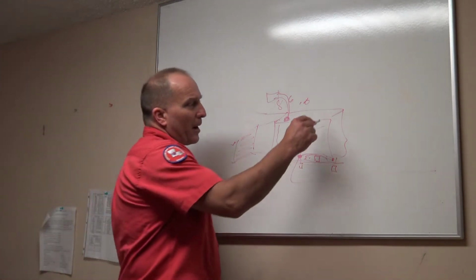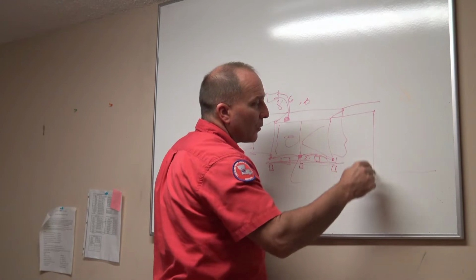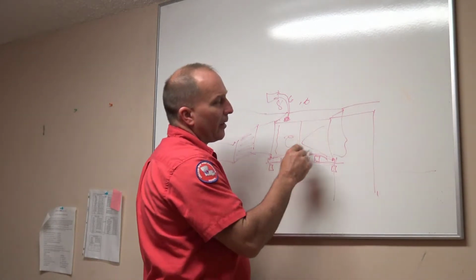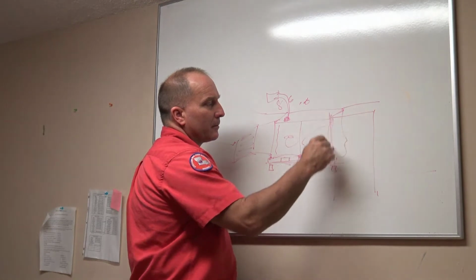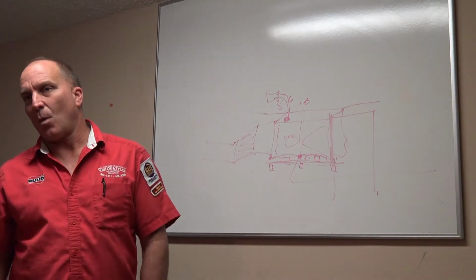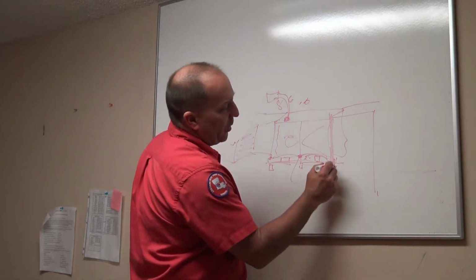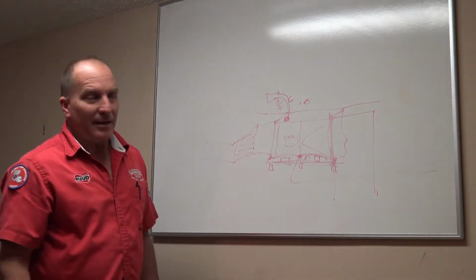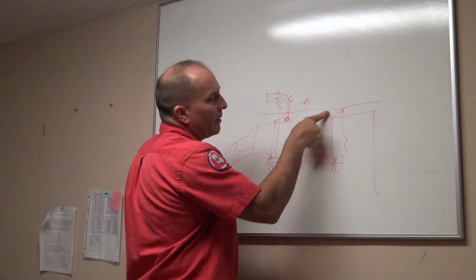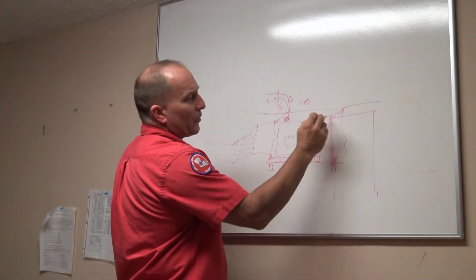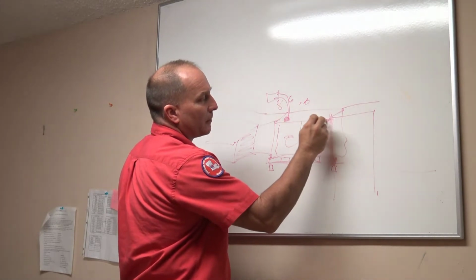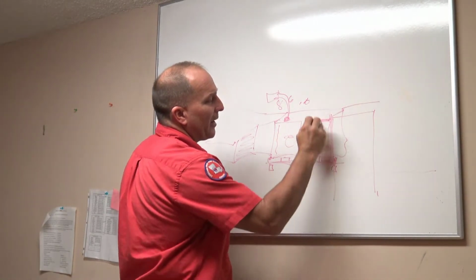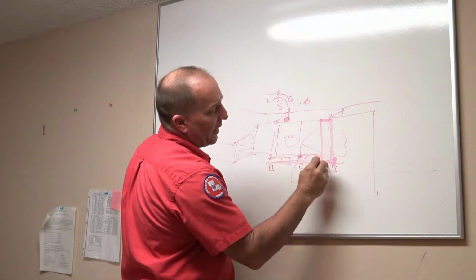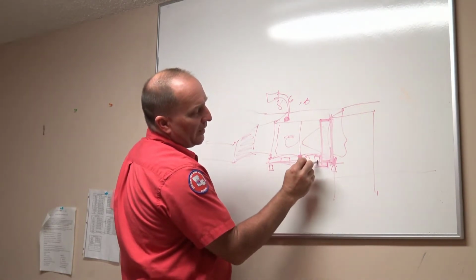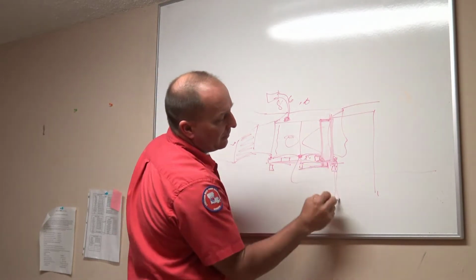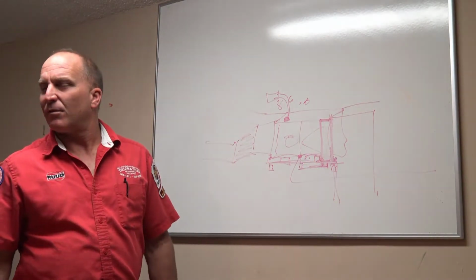Poor. What if my return air is right here? Return plenum comes down like that. Air handler butted up against my return plenum. It's not supposed to butt up against your return plenum. Why? Because my drain pan can only go up against the return plenum, right? I need a transition in between my return plenum, and now my air handler can start, so my drain pan can go up underneath here, so if I get water dripping, it drips in my pan and not down my return plenum.